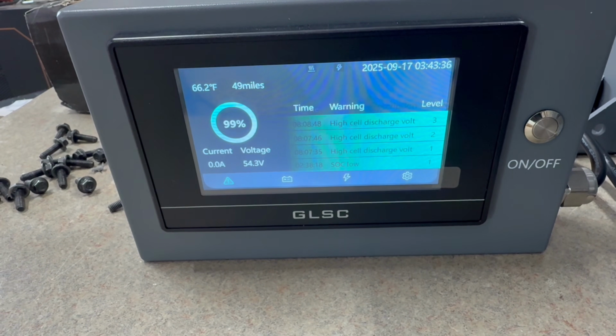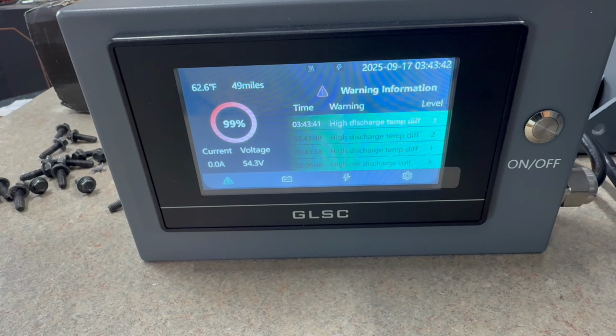All right, we've got the sensor in that cup of ice water, and it's dropping quickly. Temperature on the top left is dropping quickly. A relay just clicked. Warning, high discharge temperature. Huh, wouldn't it be the opposite? Is this a low discharge temperature?